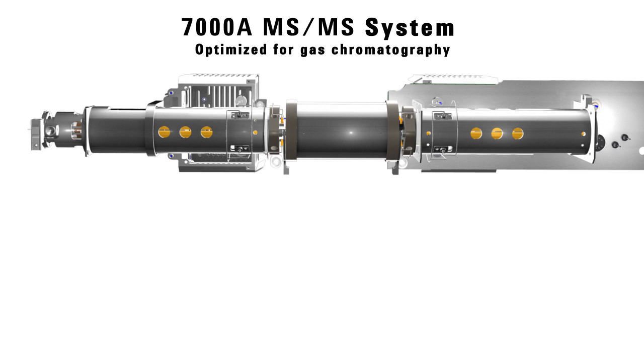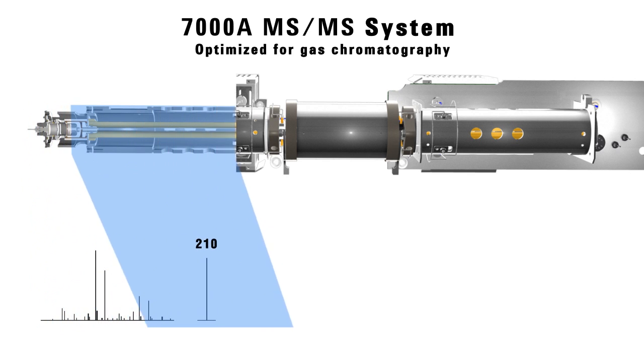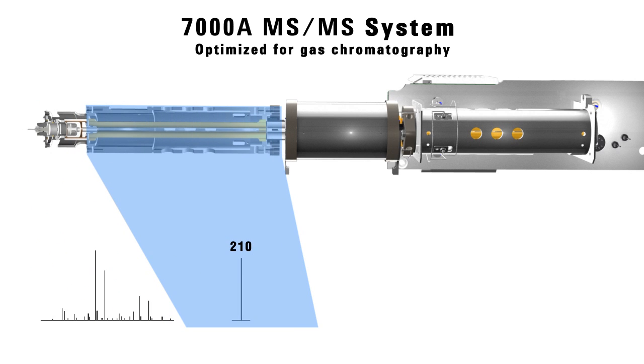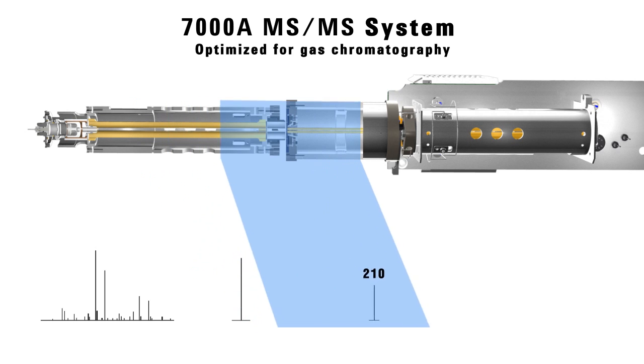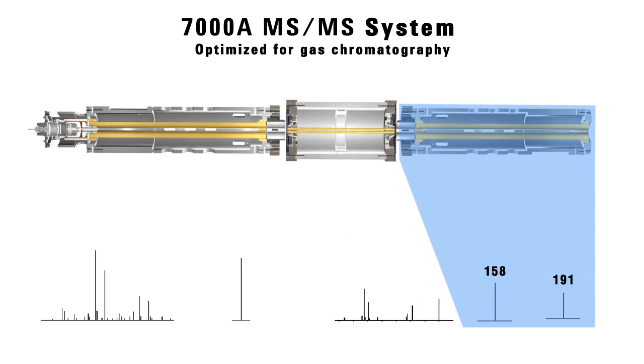The 7000A MS-MS, an MS-MS system optimized for gas chromatography. From the classical distribution of ions produced in the inert, high-performance source, to the precise isolation of the precursor ion through the path of the hot quartz hyperbolic quadrupole, into the high-pressure hexapole collision cell for efficient precursor dissociation, product ion transmission and simultaneous reduction of metastables with helium quenching, to the final accurate mass analysis in a second hyperbolic quadrupole field before ion collection at the triple axis detector.